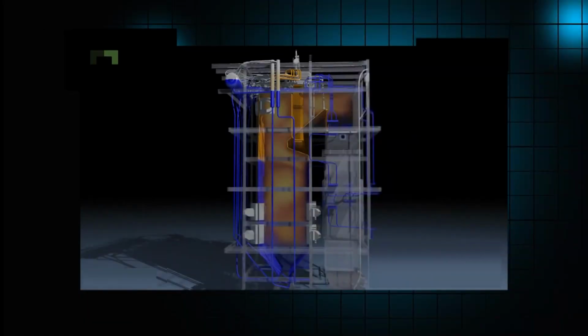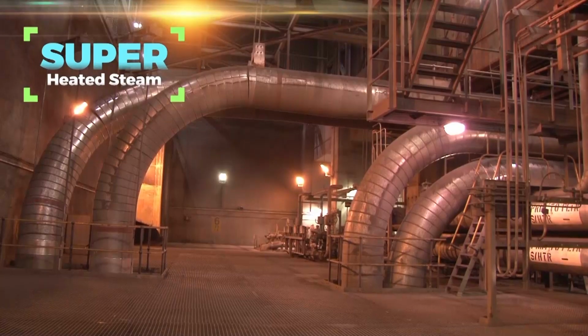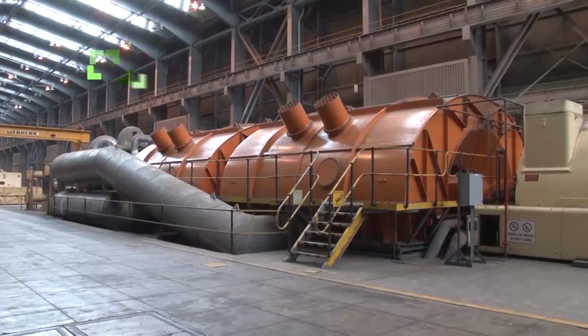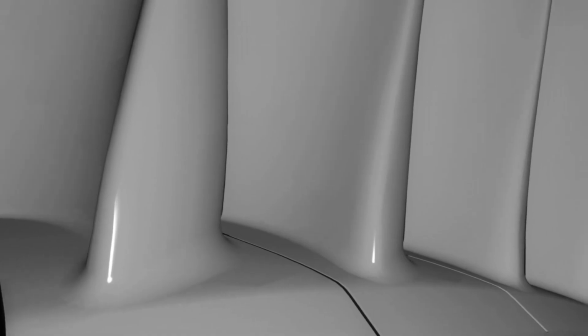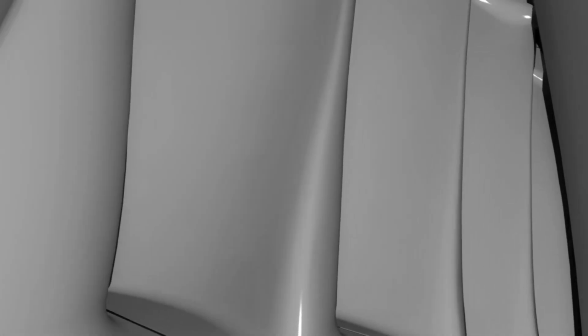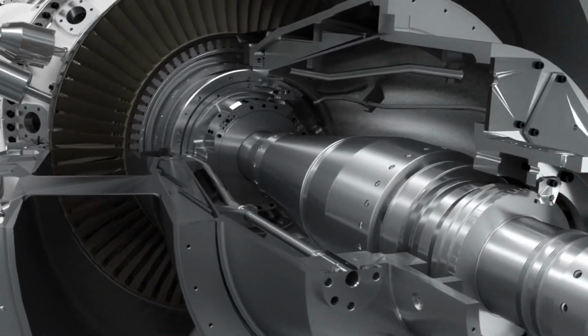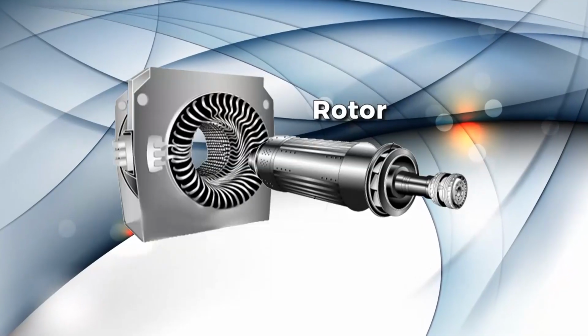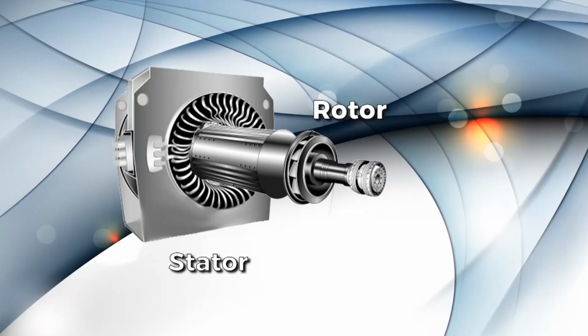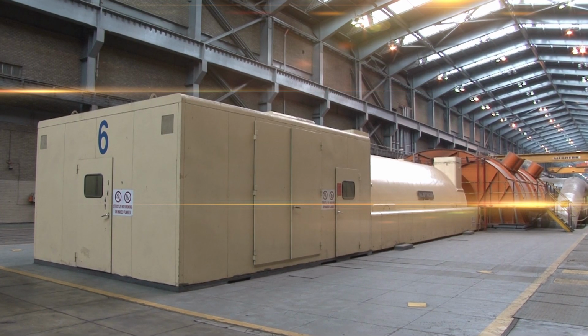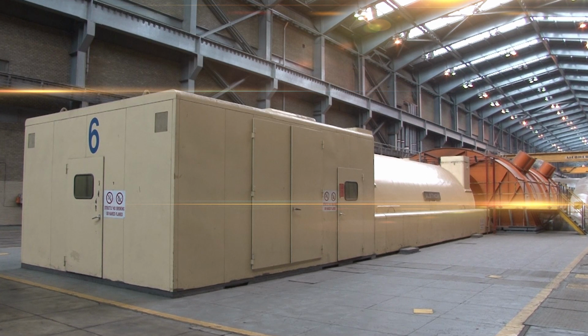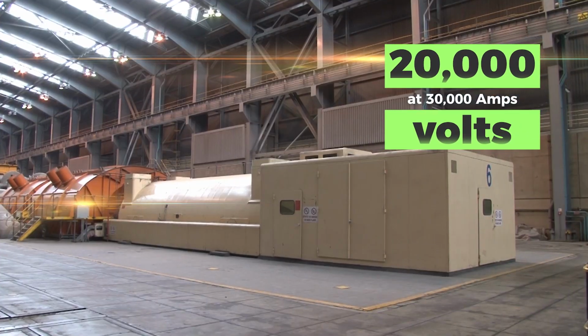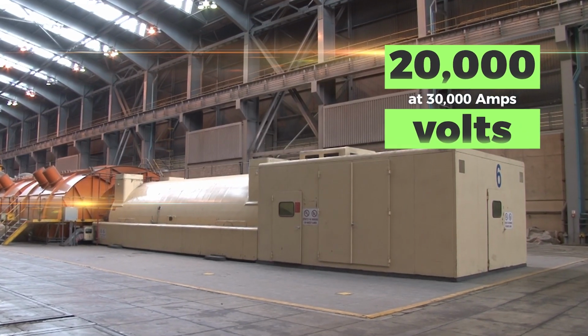Water is heated in the boiler, and the superheated steam is routed by huge steam pipes to the multi-stage turbine. The steam flows over angled blades inside the turbine, and the shaft begins to rotate. At operating speed, the turbines rotate at 3,000 revolutions per minute. The shaft in the turbine is connected to the generator rotor, spinning inside a stator, where electricity is produced. At full load, the generator generates electricity at 20,000 volts and at a current of 30,000 amps.